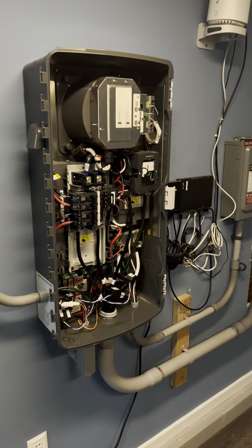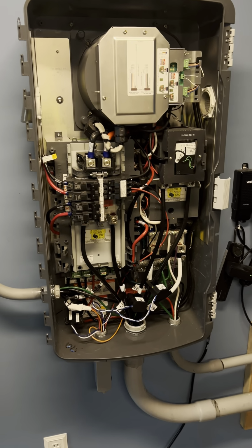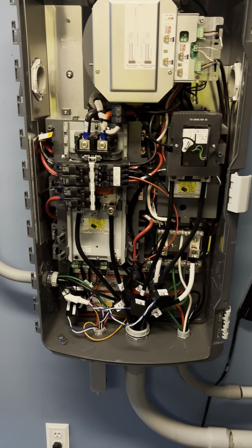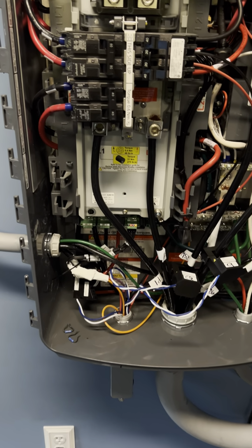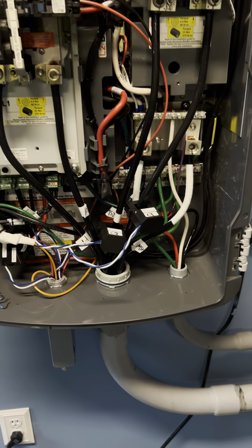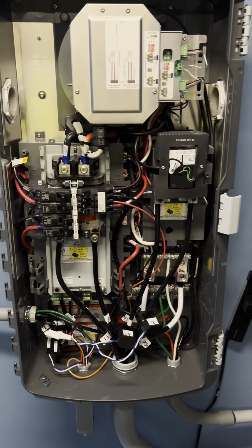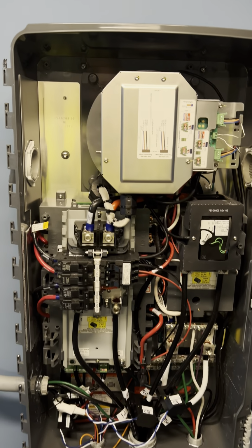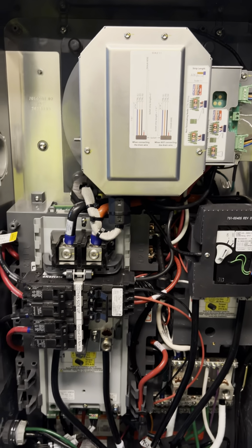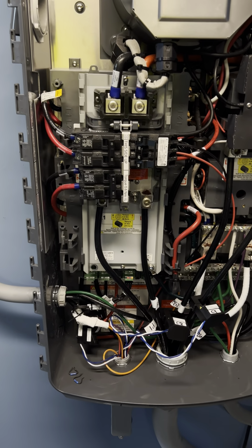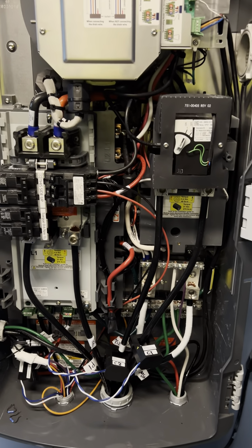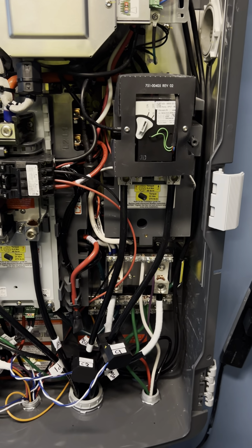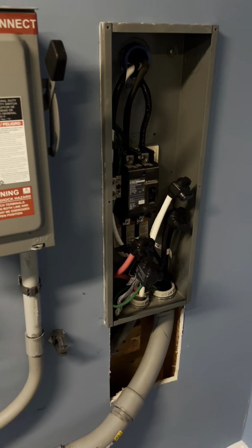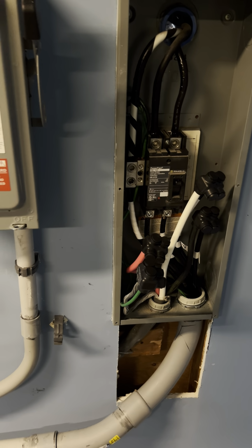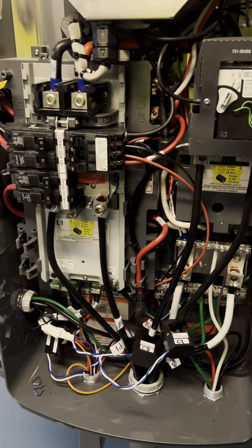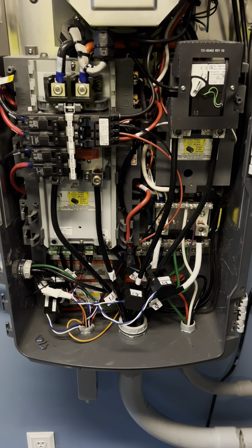This right here is our Enphase System Controller 3. Everything here is fully wired, ready to go for inspections. A lot of work here, a lot of wires. This is pretty much your main distribution for your microgrid. As you can see on the top here, we have our neutral forming transformer for all our 120 volt loads. And we don't have any circuit breakers here because we have a main service over here on the right side. Main service here, and our sub panel also is protected by a 200 amp breaker, so there's no need to have 2 of them.